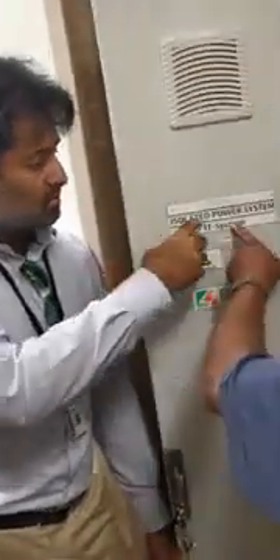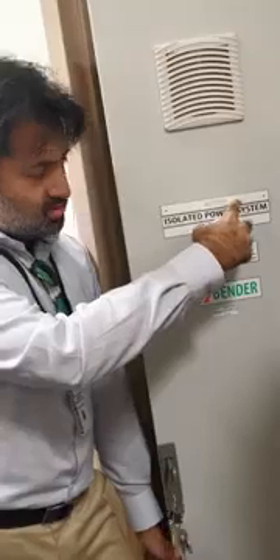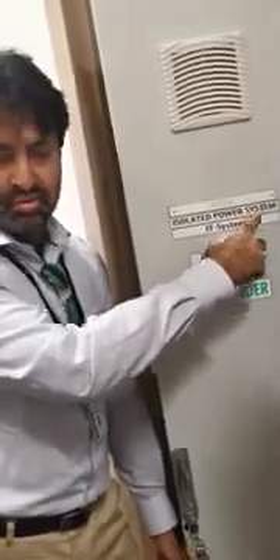So just plug it in the outlet, in the IPS outlet in the room, and as soon as you insert it, immediately an alarm is signaled by this device and also in the remote stations. And then you are able to see the panel number, which is this label, plus the circuit number, the breaker number. It comes in the display to tell you, okay, in this particular circuit we have the issue. And once that is displayed, that circuit needs to be checked and rectified, and then you can remove this plug after that. This is just for the testing purpose.